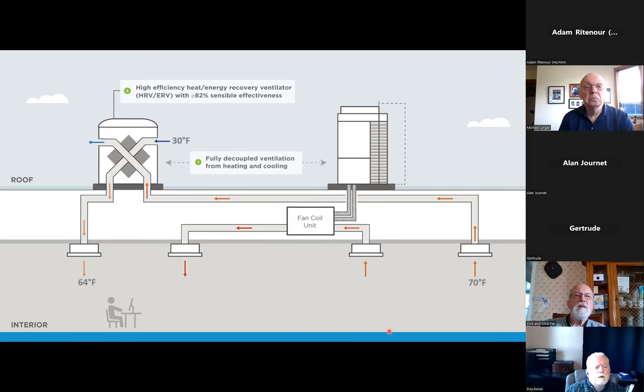So what that might look like in a building: let's say you've got a temperature set point of 70 degrees inside a space. Imagine that's us in our office, and this is our office space. So we've got a set point of 70 degrees. Let's say it's 30 degrees outside. With this high efficiency heat recovery ventilator, this outgoing 70 degree air, this stale air, will actually pre-warm this incoming 30 degree air and deliver air that's about 64 degrees to the space. And so this heating and cooling unit doesn't have that much of a lift to maintain that 70 degree set point in the room.